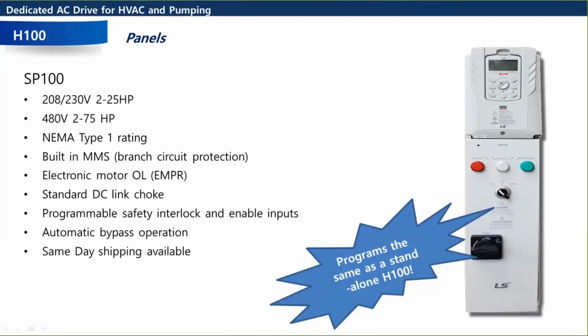It's on the shelf, ready to go. So if you order it by 2 o'clock Central Time, then you can get it shipped out the same day. So we've got built-in manual motor starters, and then recently we added in circuit breakers. So if you need like a 100K AIC package, which is a common spec in the HVAC market, these are all 100K now. So keep that in mind. It's all LS components in there, so you'll have an electronic motor overload, circuit breaker, contactors. So it's a nice package, pretty compact, reasonably priced, and we can do that same day shipping. So keep that in mind.